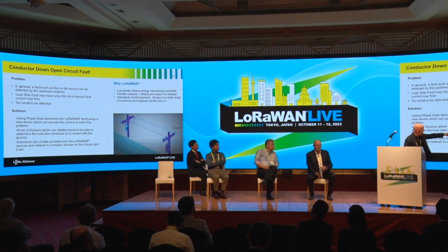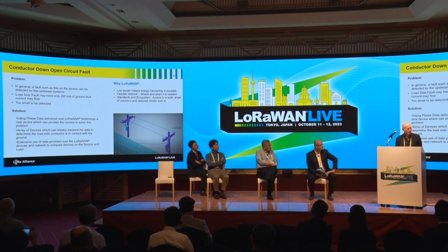You'll see here you've got a line sitting on the ground, that's on the load end of the service. But if it falls at the other end, you've got a high amount of current flowing, and the head end system understands there's a fault. It gets it. And it says, great, we've got a fault at this transformer, go and do something about it.